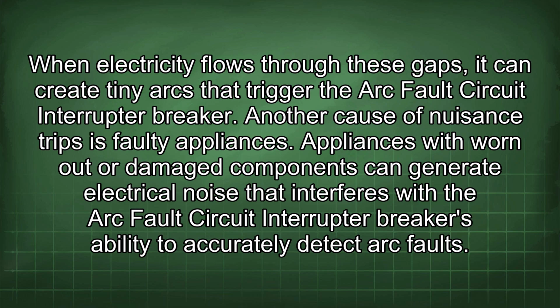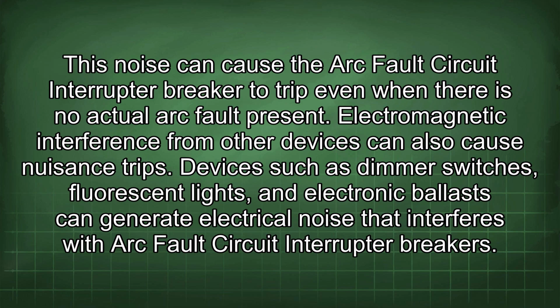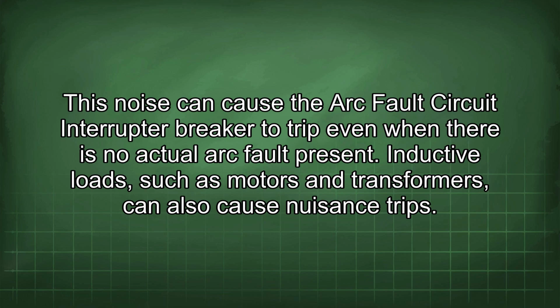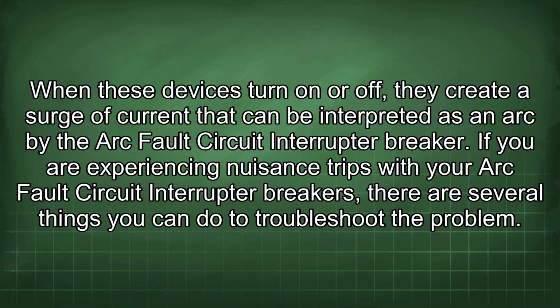Another cause of nuisance trips is faulty appliances. Appliances with worn-out or damaged components can generate electrical noise that interferes with the arc fault circuit interrupter breaker's ability to accurately detect arc faults. This noise can cause the breaker to trip even when there is no actual arc fault present. Electromagnetic interference from other devices can also cause nuisance trips. Devices such as dimmer switches, fluorescent lights, and electronic ballast can generate electrical noise that interferes with arc fault circuit interrupter breakers. This noise can cause the breaker to trip even when there is no actual arc fault present. Inductive loads such as motors and transformers can also cause nuisance trips. When these devices turn on or off, they create a surge of current that can be interpreted as an arc by the arc fault circuit interrupter breaker.